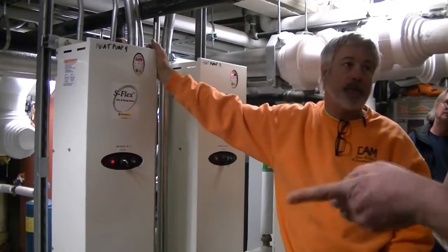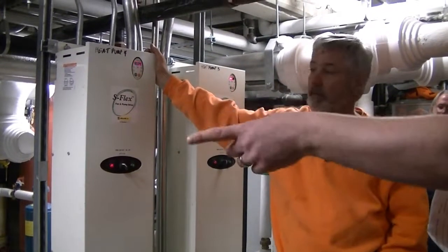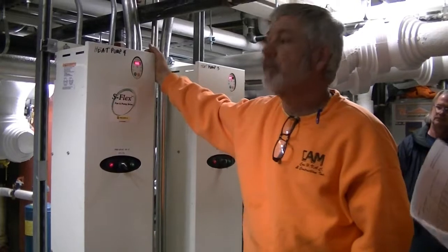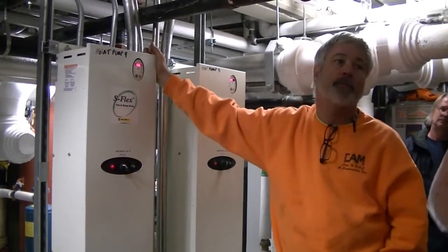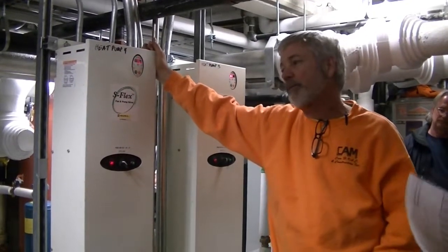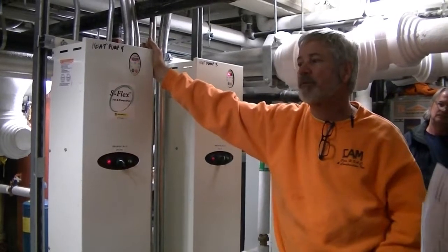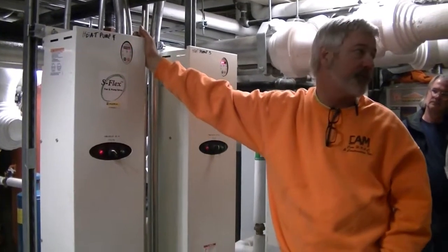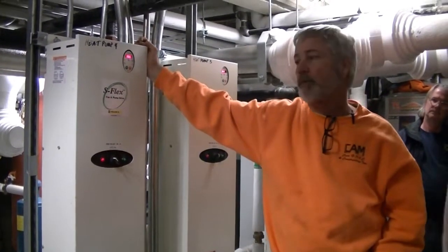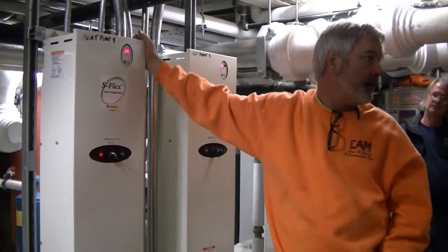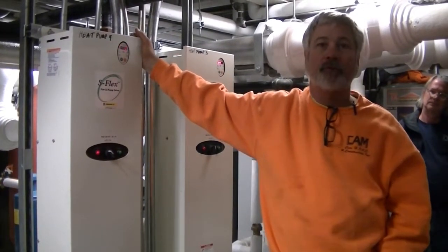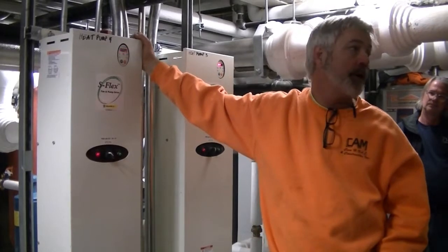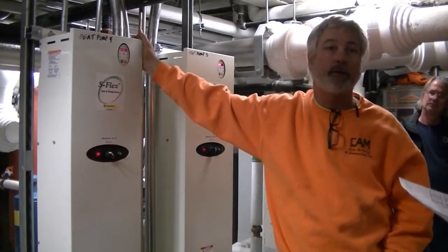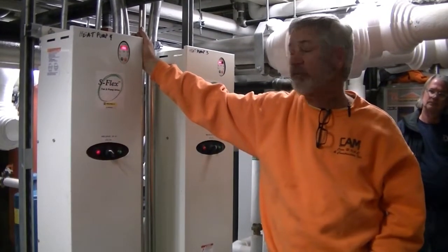What are safe differential pressures, and at what point should they be worried? Well, the system's based on like a 14-pound differential pressure. If you're upwards of like 18 to 20, you've got to start getting concerned. If it goes higher than that, you really have to be concerned. Something's going on. Either somebody shut a valve, or something got plugged up.